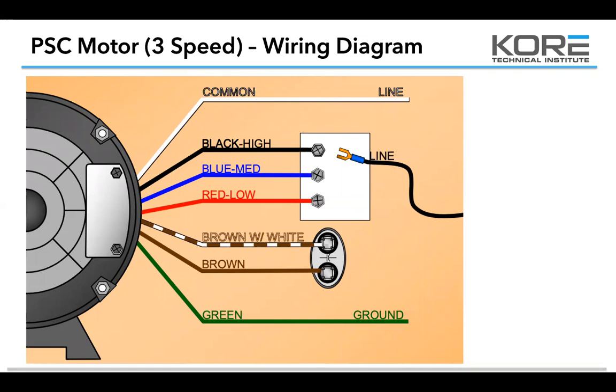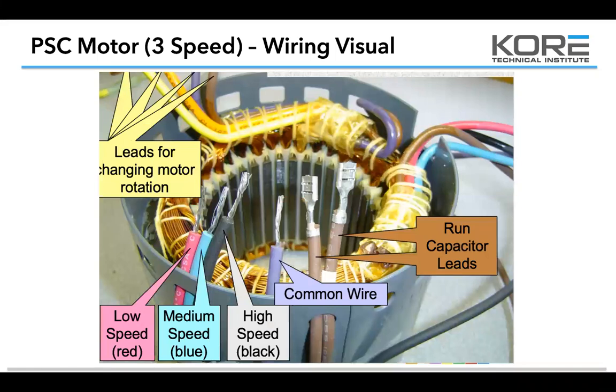If you're dealing with a blower motor in your application, you're going to have your common line coming in. If it's 230, that could be the other side of your 230 or 208. If it's a 115, that's going to be your neutral. And then you're going to have your 2 brown wires coming out that go to your run capacitor. And then you're going to have your ground. And if you're dealing with a directional motor where you can change them, you're going to have 4 more leads come out, like what you see in this picture right here. The yellow block shows you the 4 leads for changing the rotation of the motor. You've got your line voltage leads where you're going to hook up your common and either your low, medium, or high speed, and then you've got your 2 brown wires that are for your run cap.